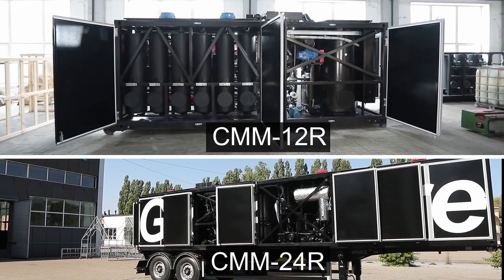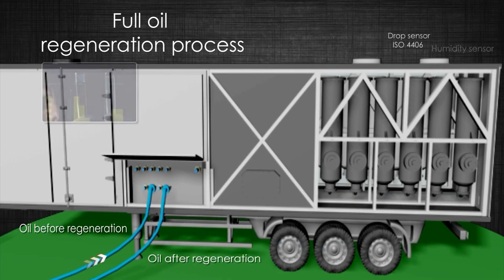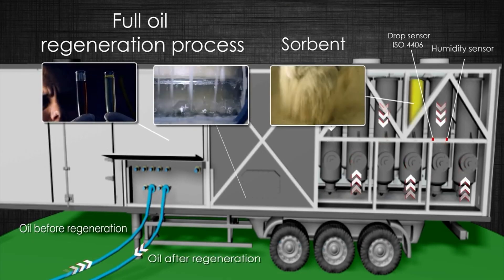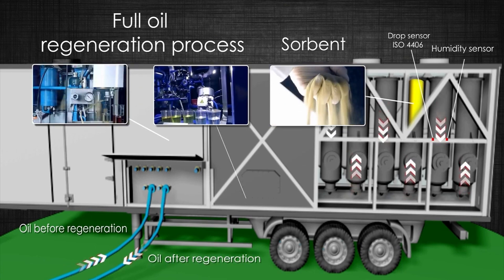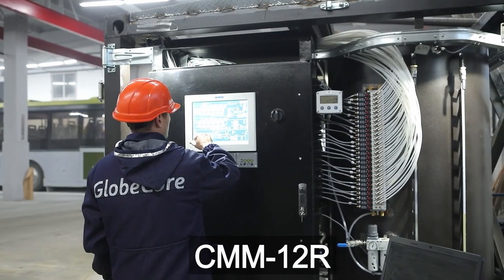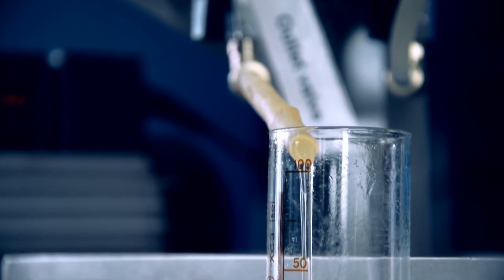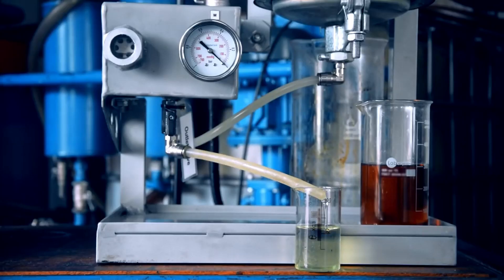In the general case, the sorbent gradually becomes saturated with impurities and over time needs to be replaced and disposed of. The main advantage of GlobeCore technology is the possibility of reactivating the saturated sorbent without discharging it from the columns, after which the reactivated sorbent can be reused for the clarification of base oils. The sorbent can be reactivated up to 500 times or more, which is equivalent to several years of operation of the regeneration equipment.